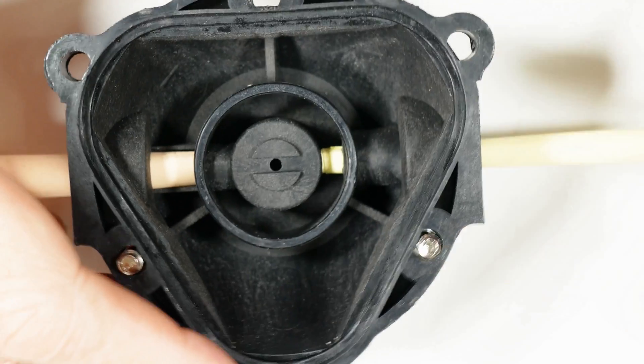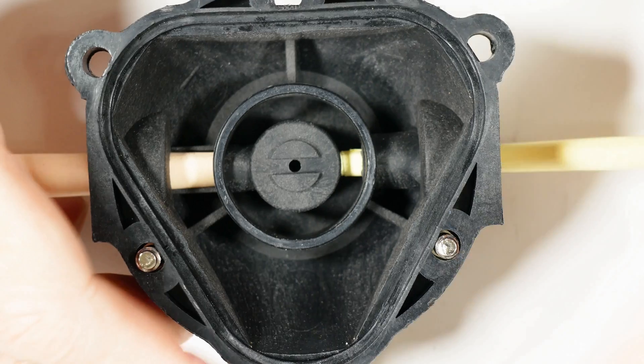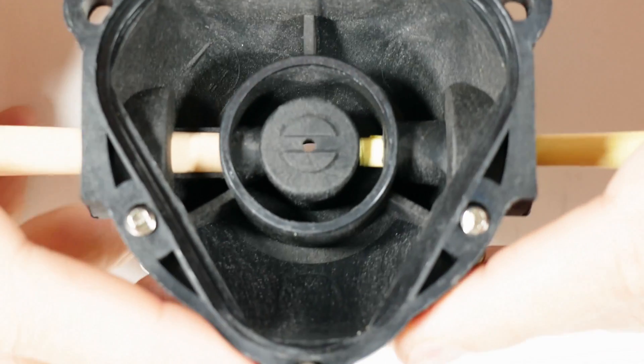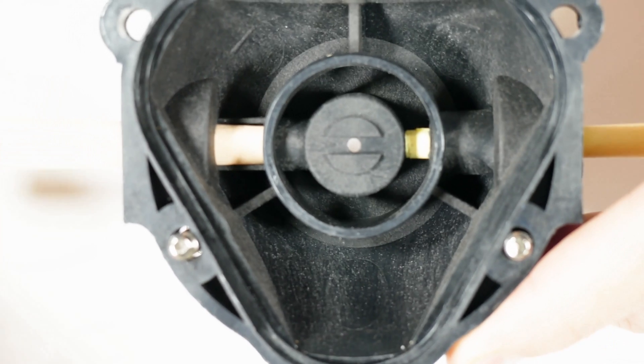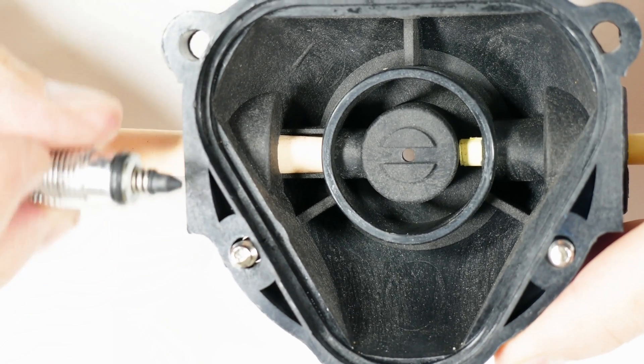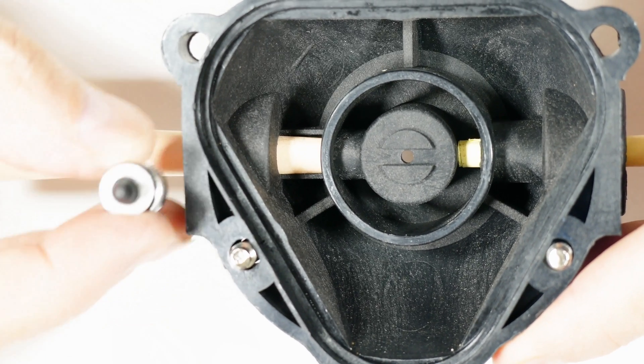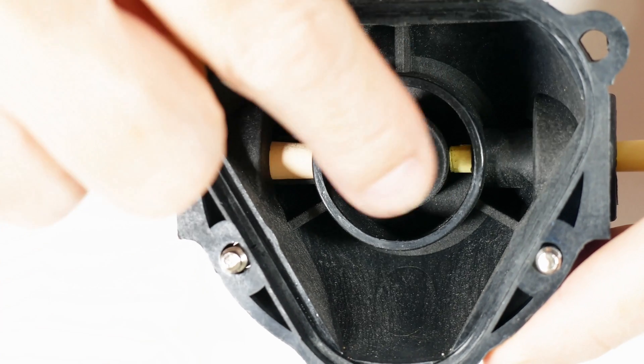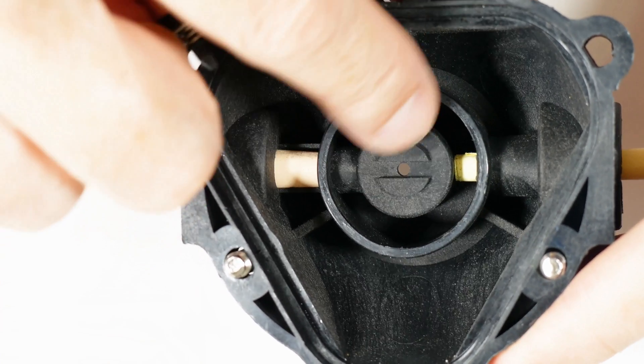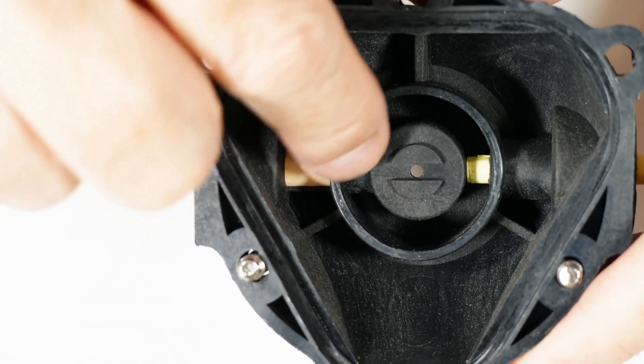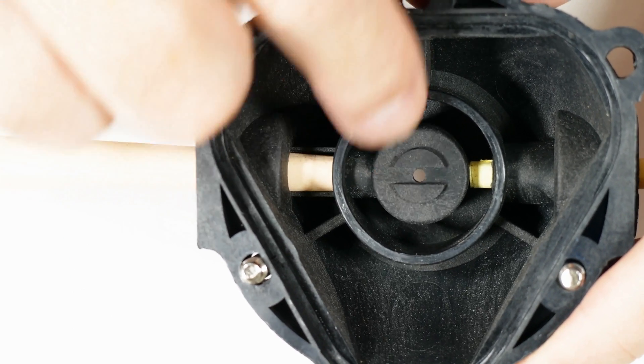Water comes in here into this chamber, it's pulled into the cylinder, and then when it is forced out of the cylinder it comes into this chamber. From this chamber it goes out of this yellow tube. The only thing we're missing now is that center hole. Normally this valve we talked about earlier is on the back side of there pushing in, and this will limit the pressure.